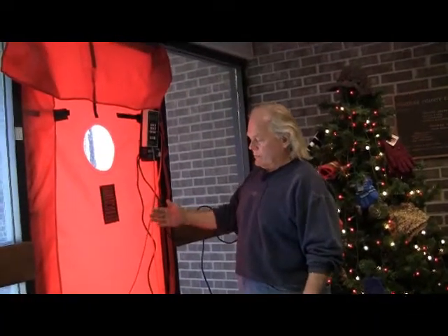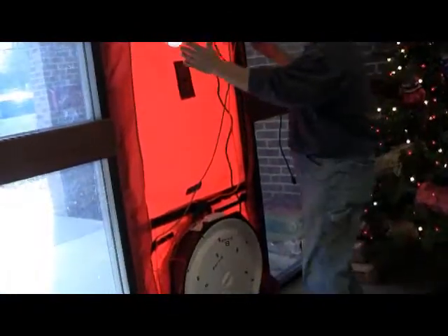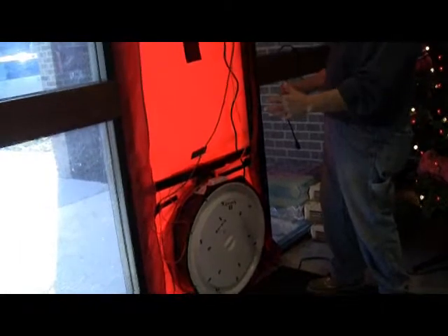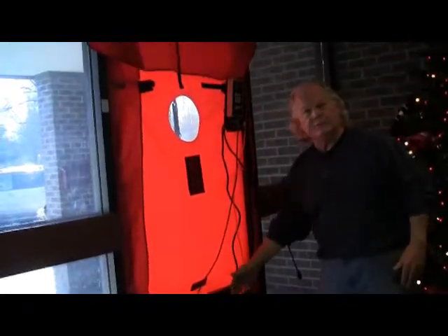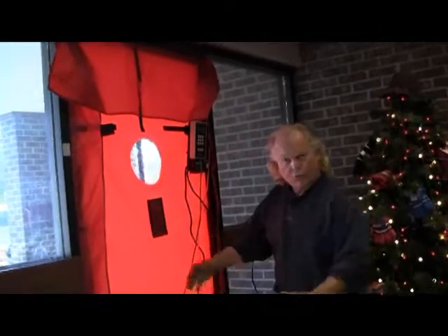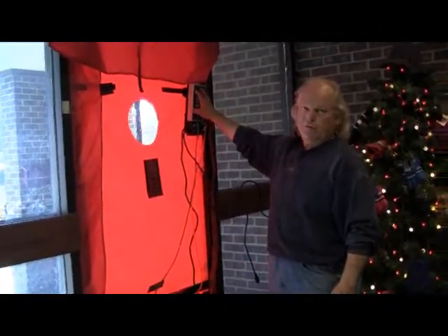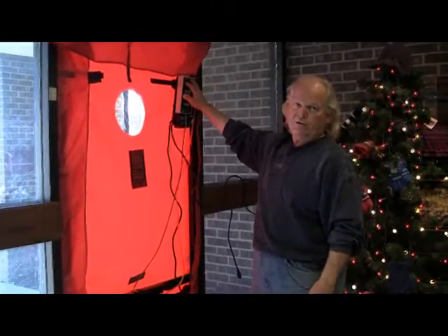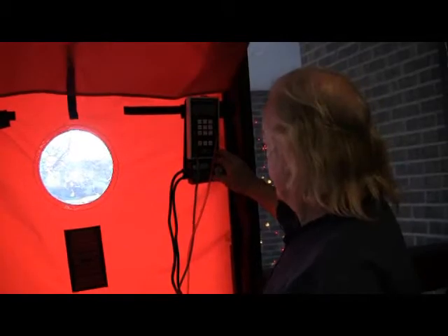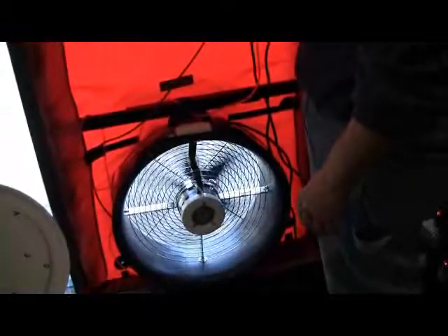We've set up a blower door, which is a large calibrated fan that fits in an adjustable frame with a Dacron cover so that we can actually have a closed door with a fan system in it. This allows us now to either depressurize or pressurize the building, know how much flow is going through the fan, and understand what the leakage characteristics of the building are. So we're actually going to turn on the fan controller and start moving air out of this building.